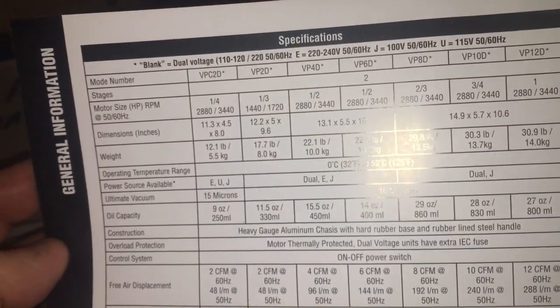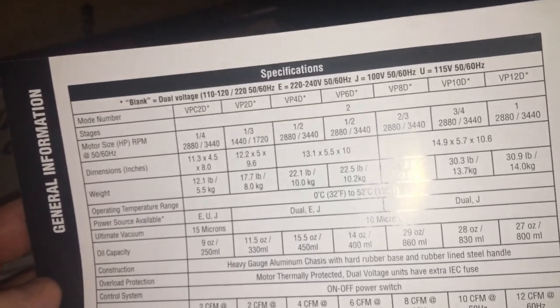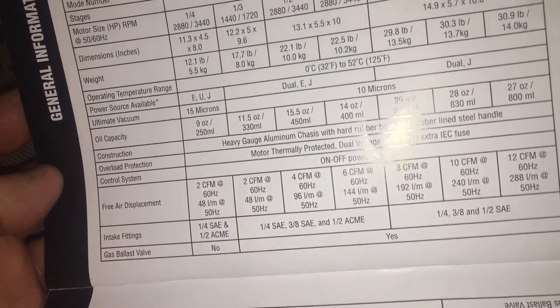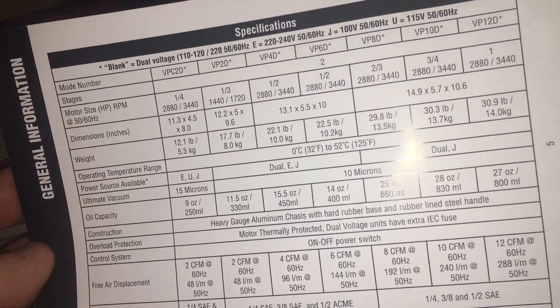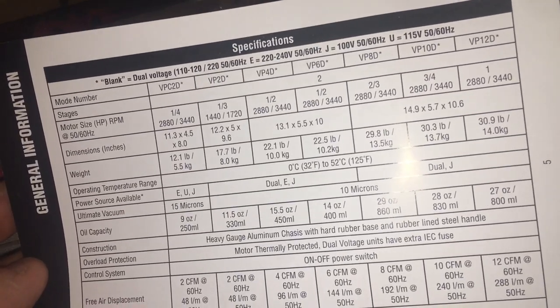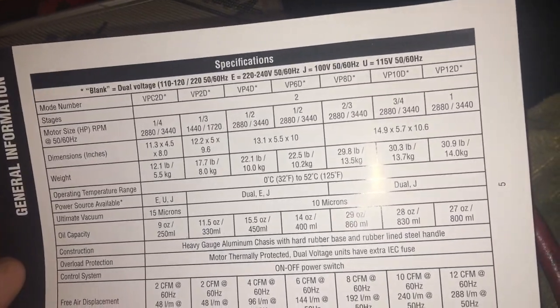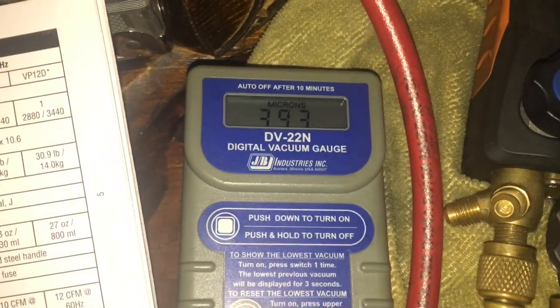I'm trying to get a pump down around 10 or 12 pounds — just under 15 pounds would be nice. So I guess the only option is a 2 CFM two-stage that gets down to 15 microns. That would be only about 3 pounds heavier than what I've got here. At 7 minutes, we're at 393 microns.